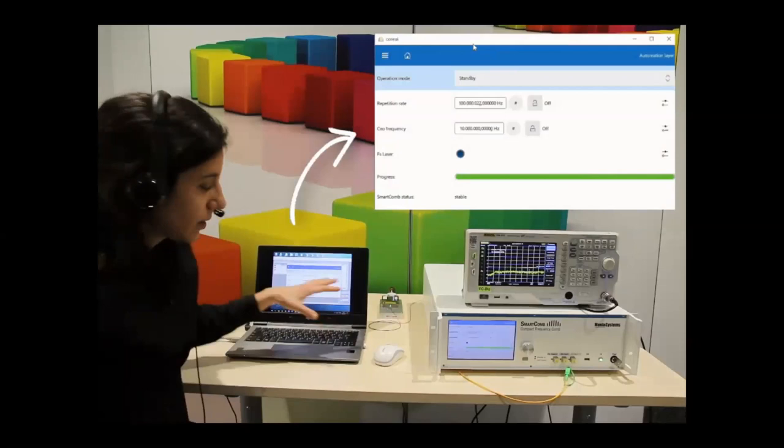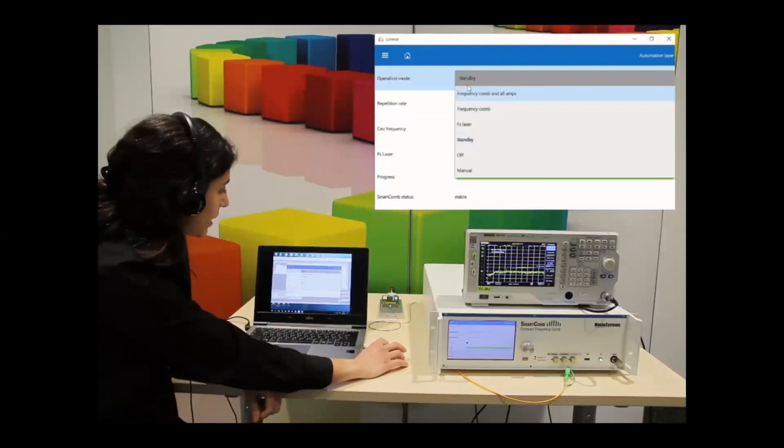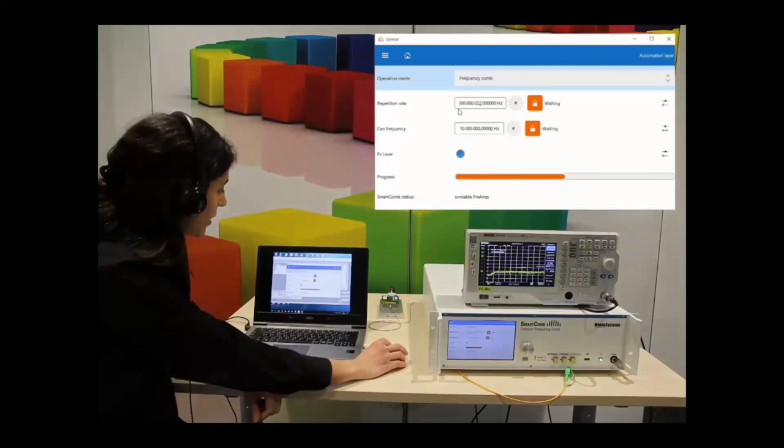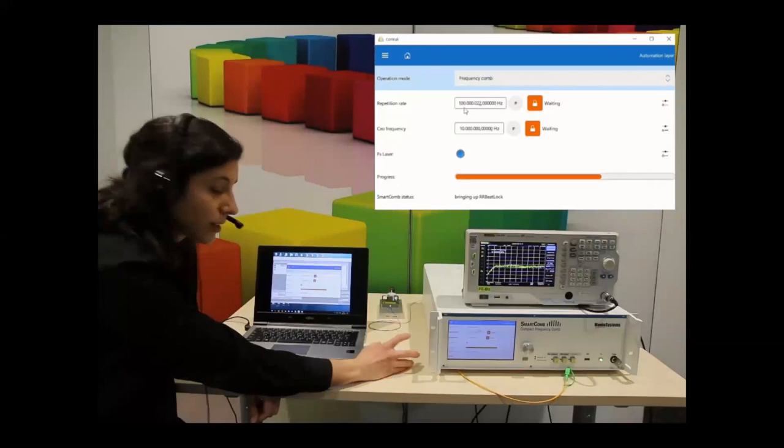So the first thing that you would need to do to switch it on is go to this drop-down menu and change from standby to frequency comb. What you see here is the repetition rate of the SmartComb. And here in the other box is the carrier envelope offset frequency.